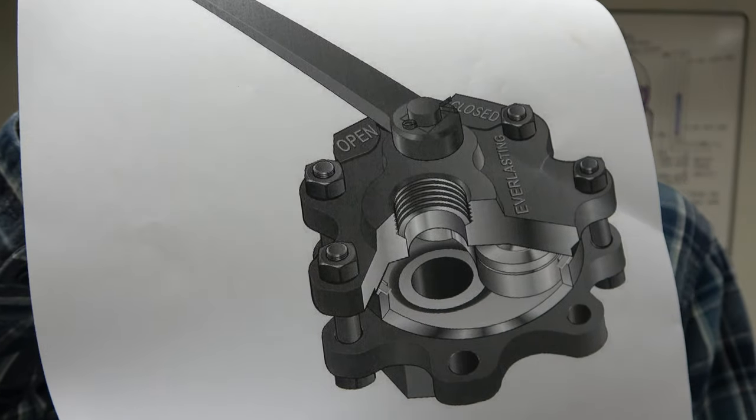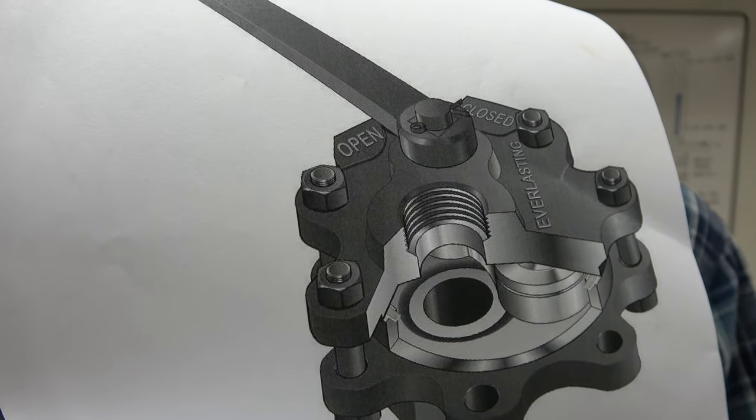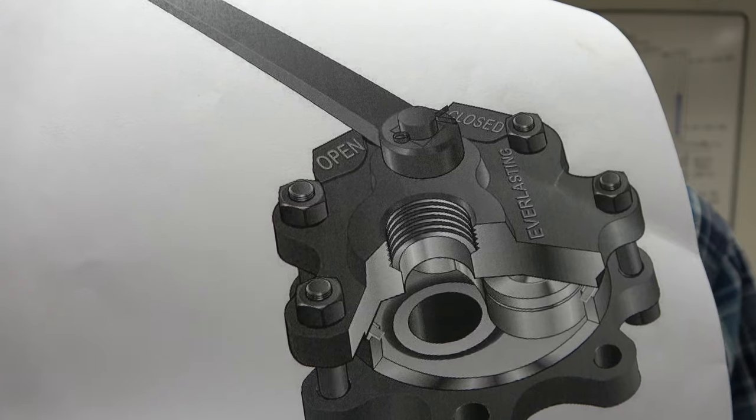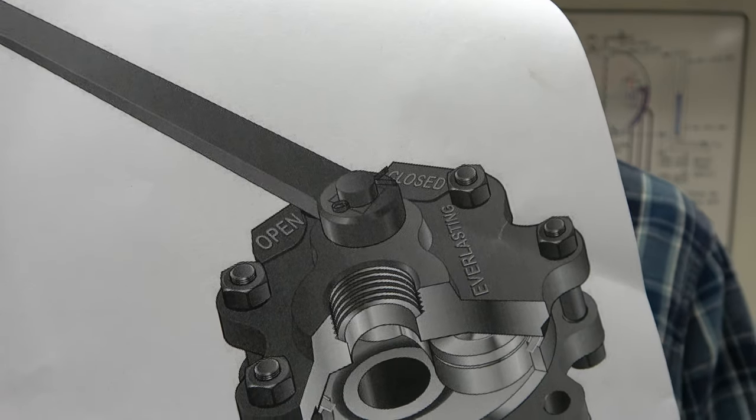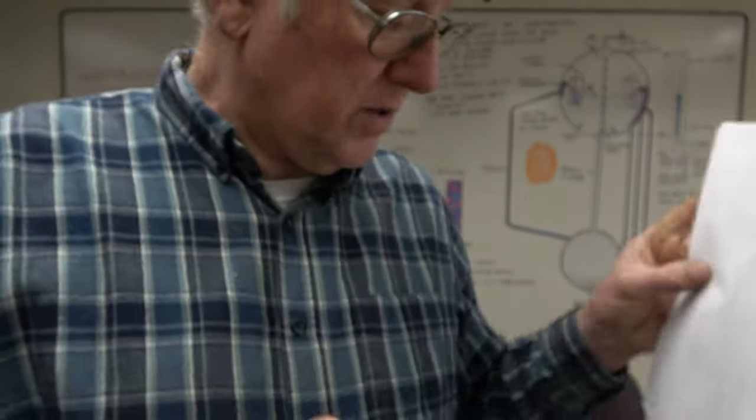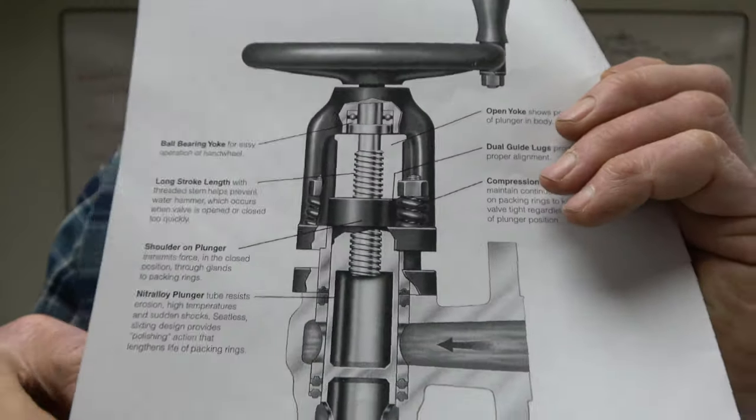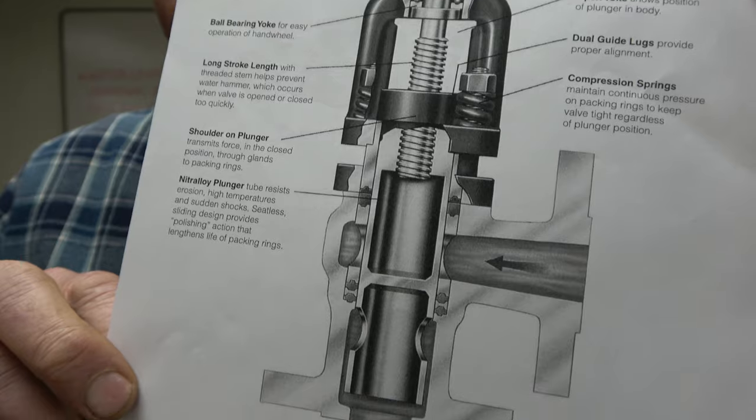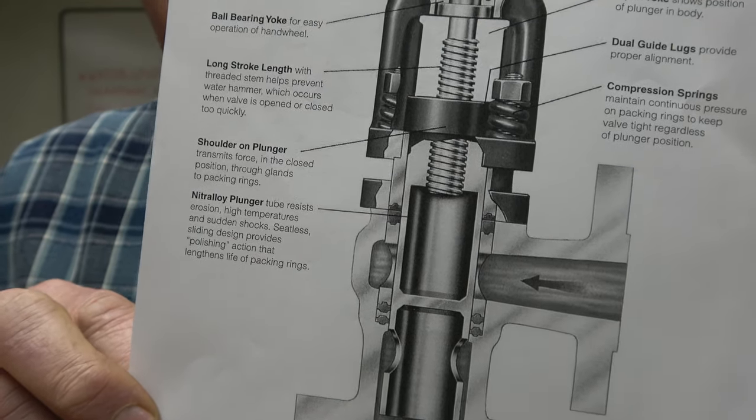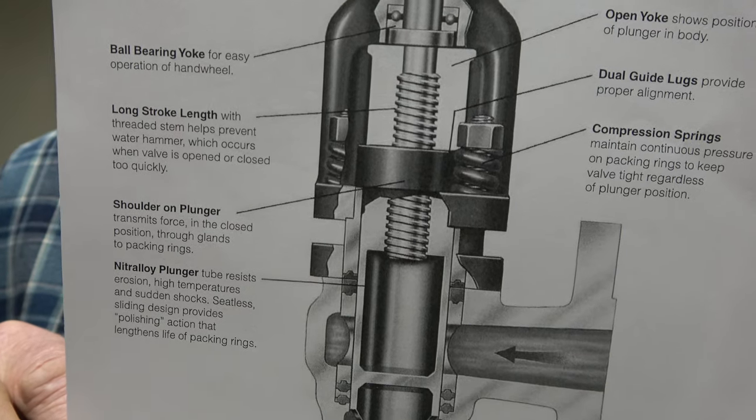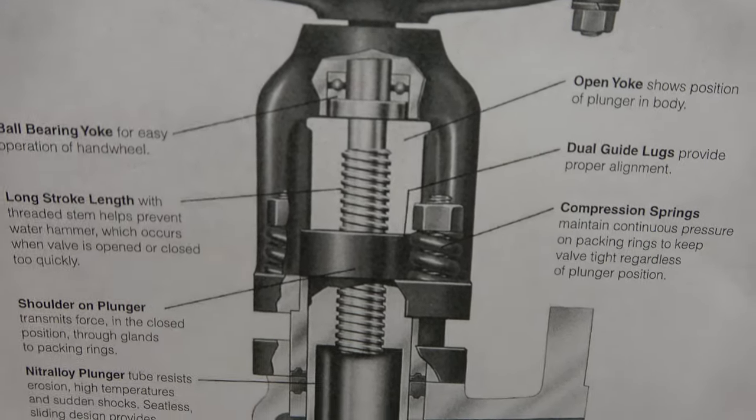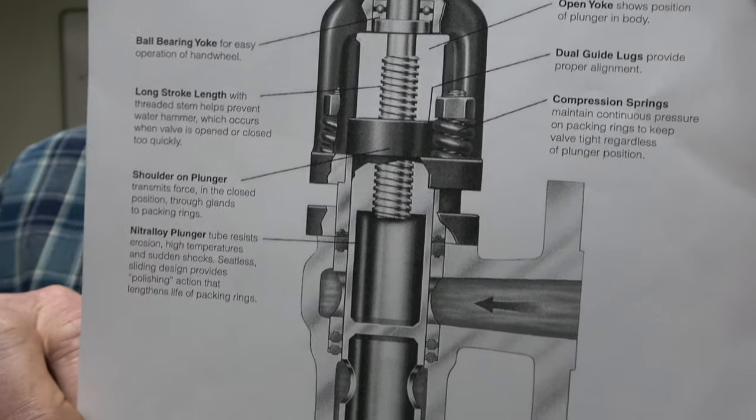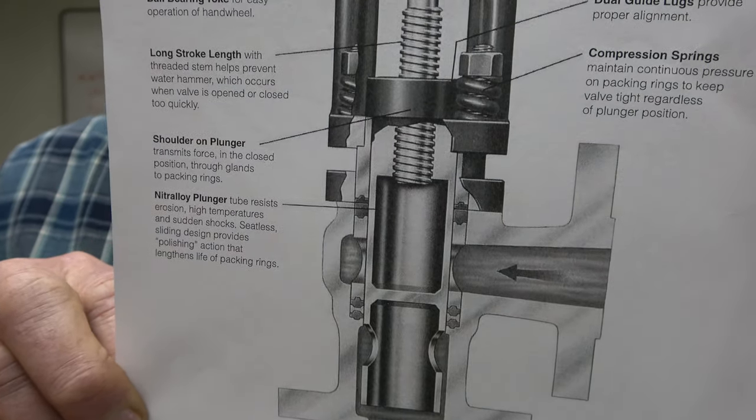This is a quick opening valve. It's an Everlasting valve manual. It shows a lever. There's a plug that comes across the opening. This is your first blow-off valve. The purpose of this is to provide a sealing valve. It opens quickly. Do not blow down with this, it slams the water too fast down the piping, causes water hammer. This is a second seatless blow-down valve. There's a plunger in the center. You open that up and there's some sealing strips. This allows a little more controlled flow. This one's fully open and then you fully close it. The length of time to open depends on the size of the boiler, how much you're blowing down. But you can't leave it open too long and start losing circulation in the boiler. These are a lot of Everlasting valve manuals. They have some really good reference material.